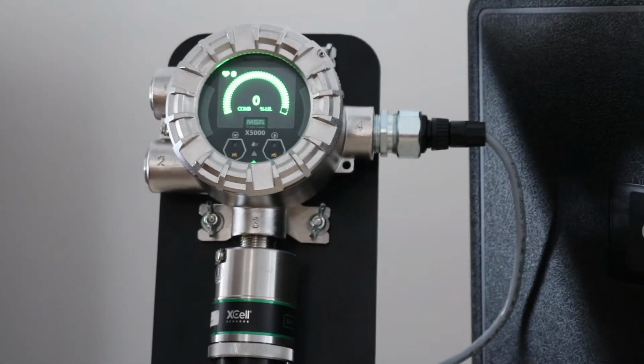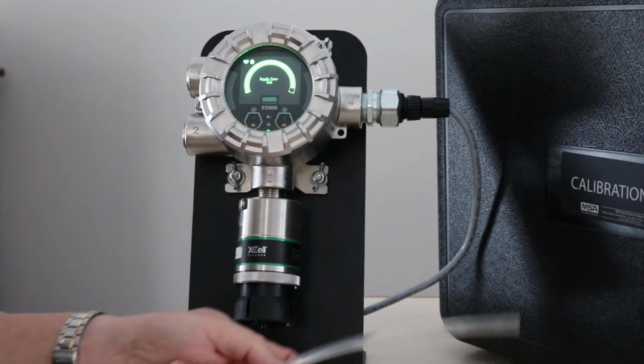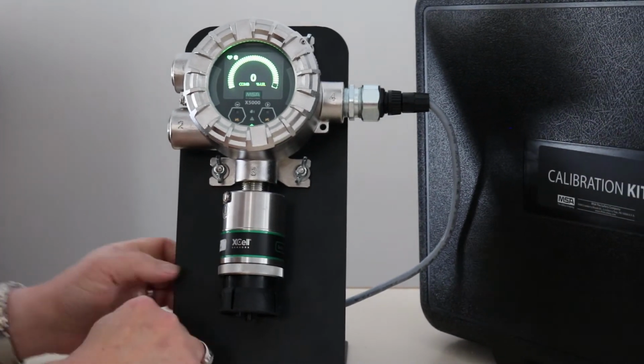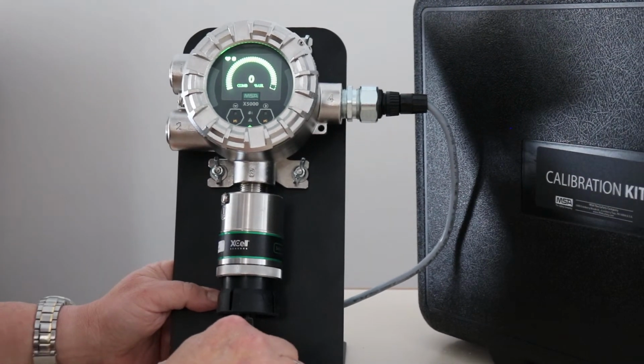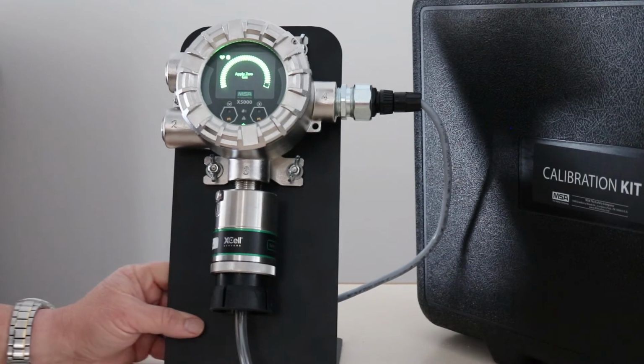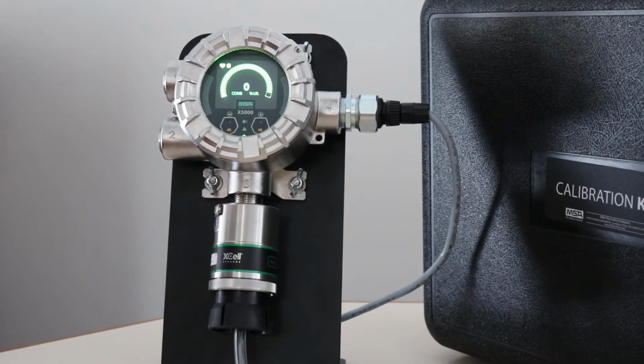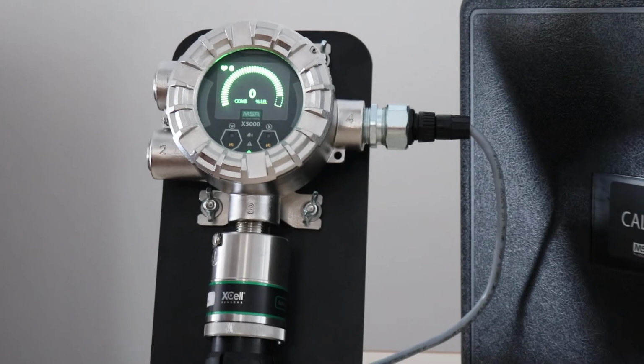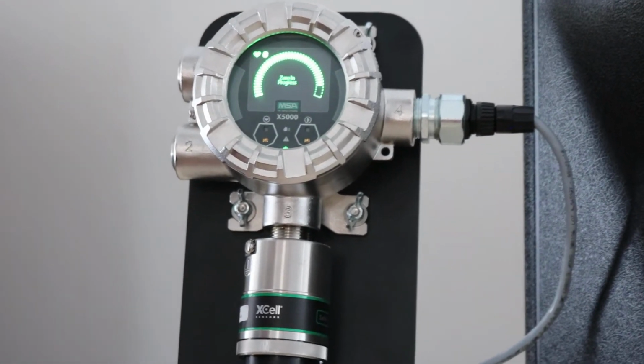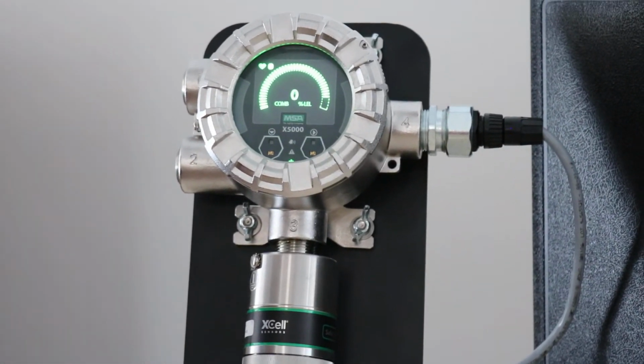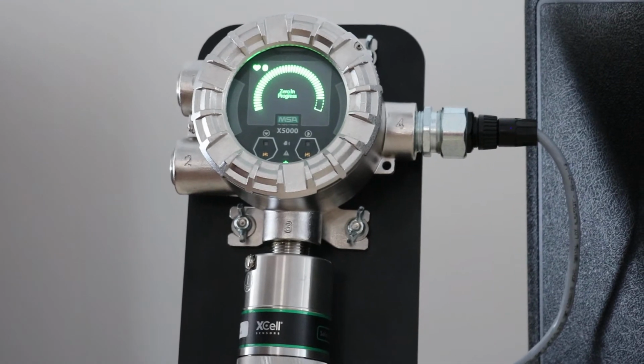And it is looking for the gas. So I will take the zero gas and connect. You always start with the zero gas, and as you'll see, it's starting to count down. Within the calibration kit, I'll take this time. I do not want to edit this time out because I want you to see how long this procedure takes.